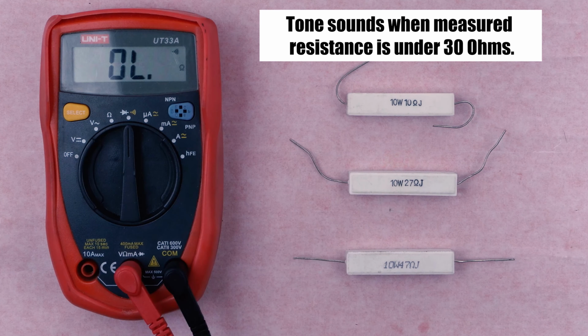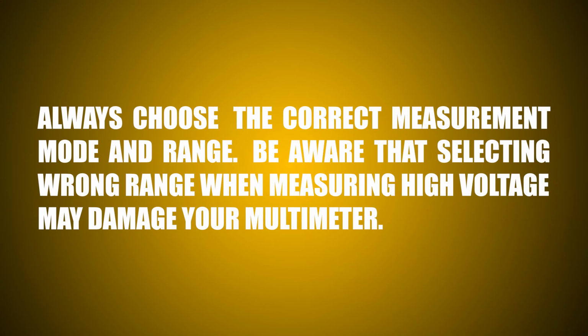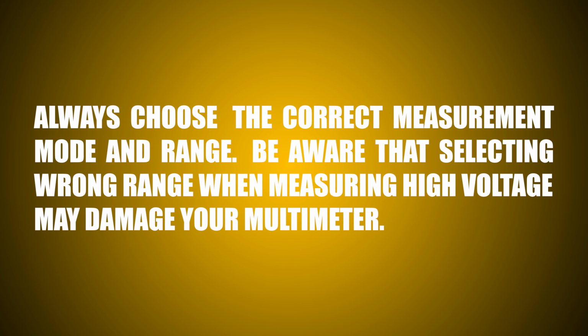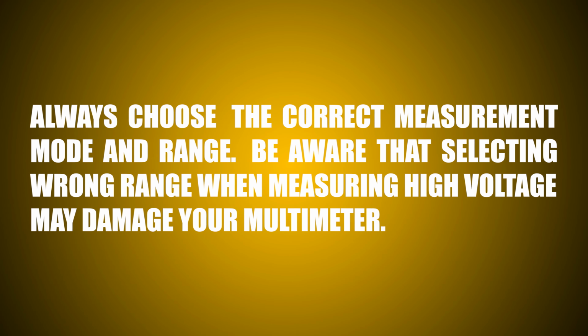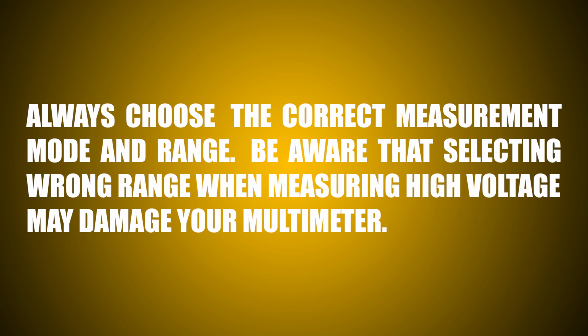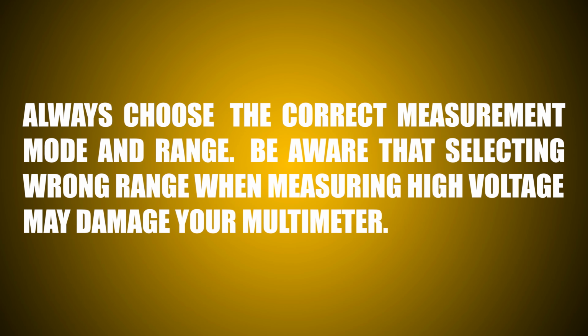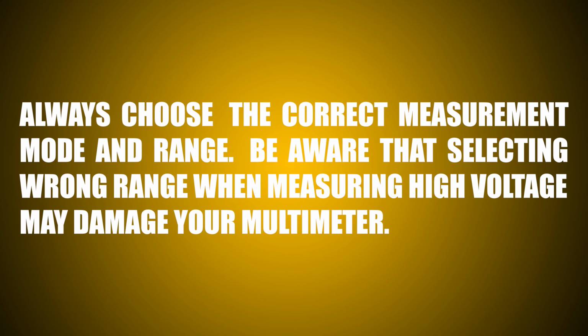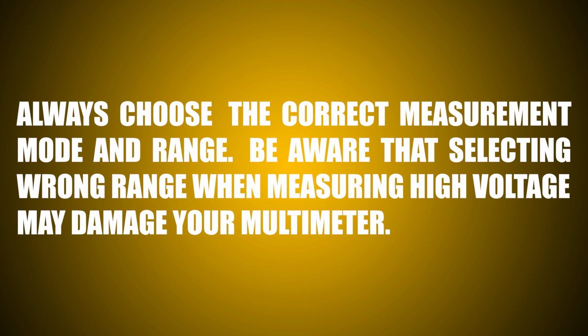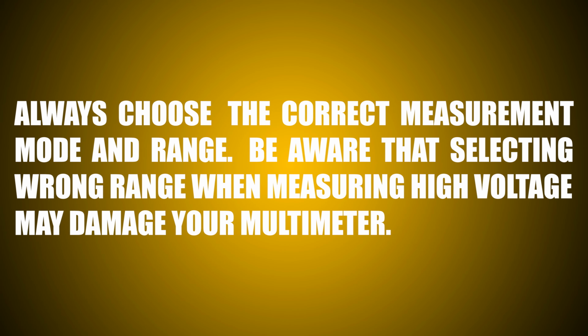Okay, we are now ready to formulate the first and basic rule that needs to be learned. Always choose the correct measurement mode and range based on the characteristics of the signal you are measuring. Be aware that selecting a wrong range or mode when measuring high voltage may damage your multimeter.